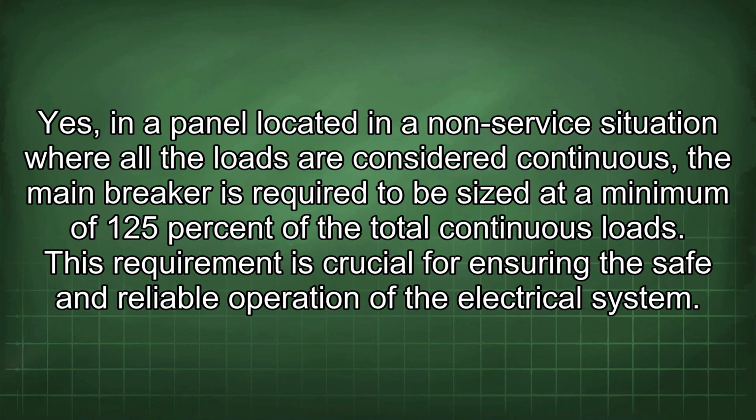Yes, in a panel located in a non-service situation where all the loads are considered continuous, the main breaker is required to be sized at a minimum of 125% of the total continuous loads. This requirement is crucial for ensuring the safe and reliable operation of the electrical system.